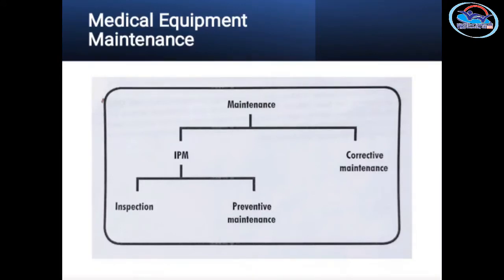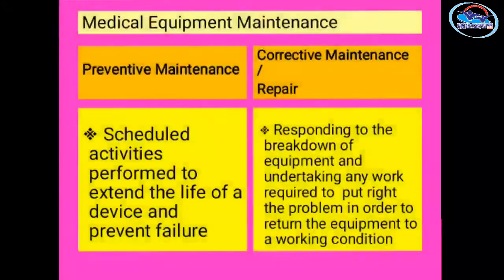Preventive Maintenance involves scheduled activities performed to extend the life of a device and prevent failure. For medical equipment, this follows a schedule — for example, a microscope or multi-parameter monitor must be serviced at regular intervals such as every three or six months. A service engineer performs preventive maintenance on the equipment at these scheduled intervals.